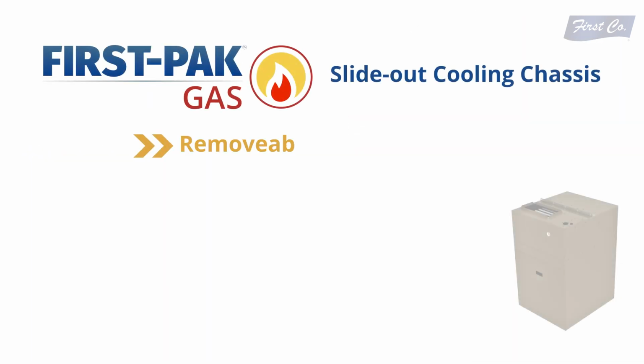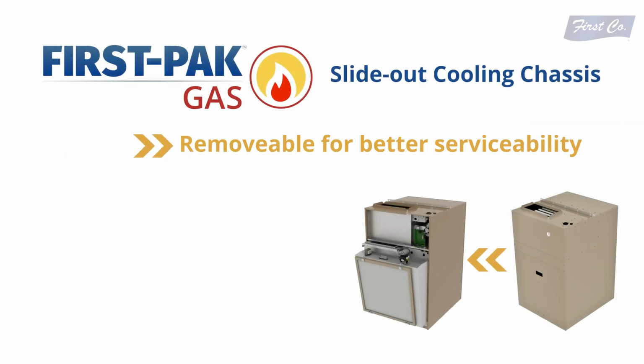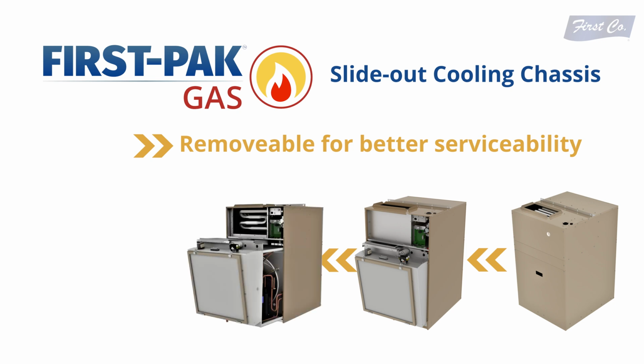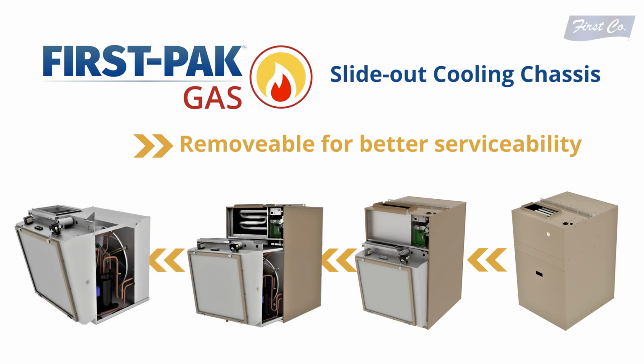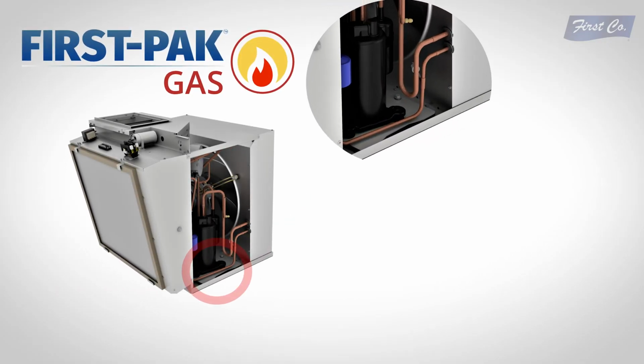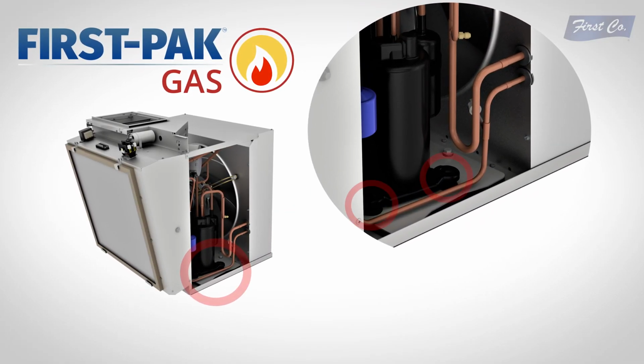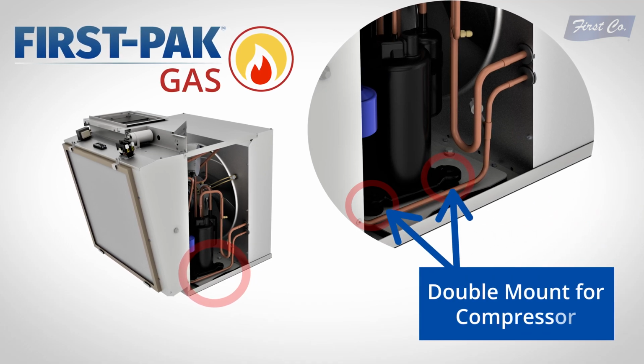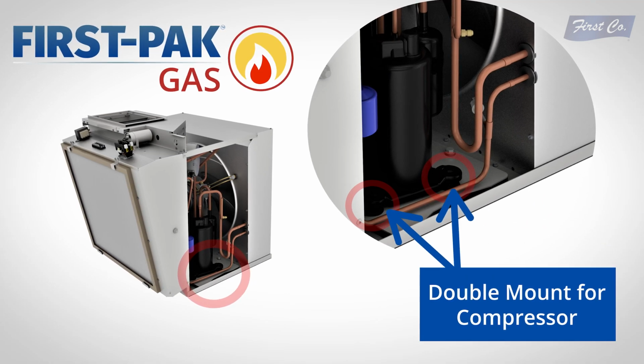The cooling chassis is in the bottom access panel. It comes pre-charged and pre-wired, which is one of the best features of this unit — you don't have to do anything service-wise. If you do, it's made to be removed and serviced on the floor or on your bench. One of the better features of this cooling chassis is that the compressor is double mounted, which helps reduce vibration and noise coming off the compressor during cooling mode.